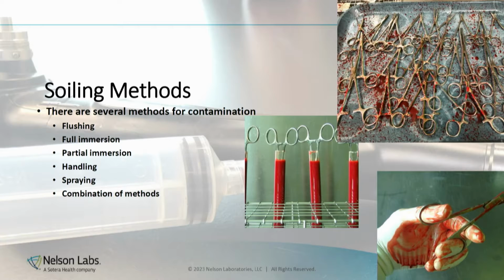The next step is soiling methods. How is this device soiled, right? No more immersion, spray, whatever you want to do, direct inoculate. All that is out the window. Now you have to simulate it, right? You have to see, does it get handled during surgery? Let's handle it. What portion is immersed into the body? What's going to immerse in there? What portion will be sprayed? Oh, the cable might get sprayed. Let's focus on that, right? So the method of soiling is as important as the selection of the test soil.